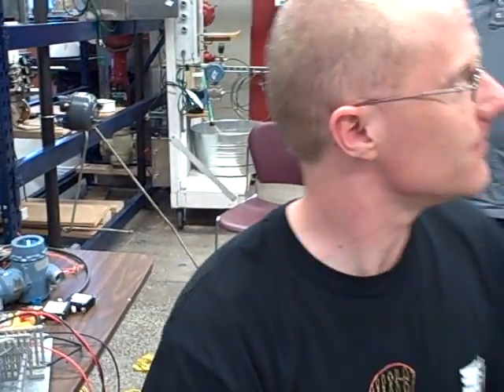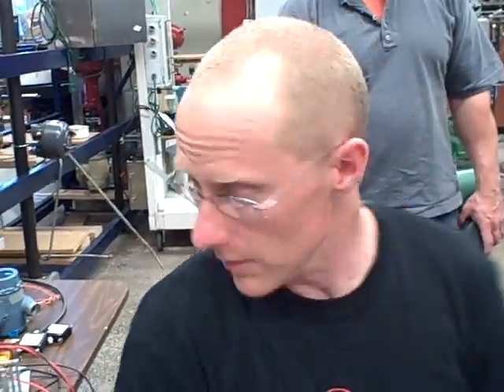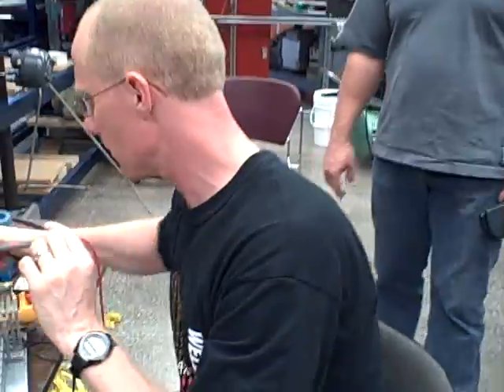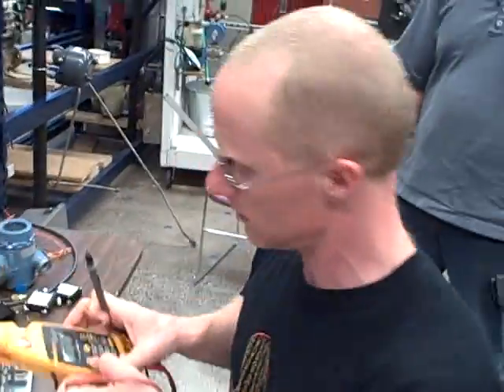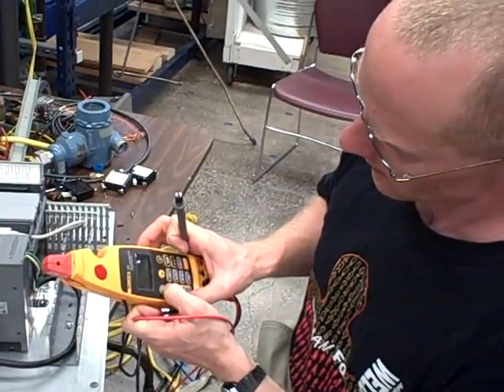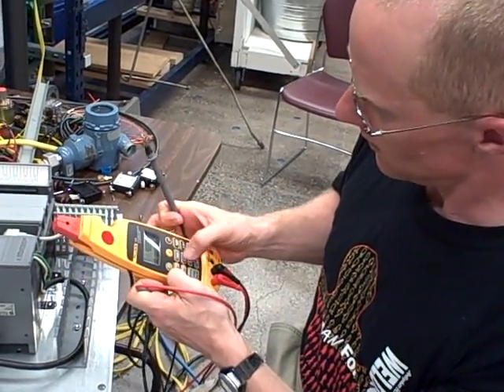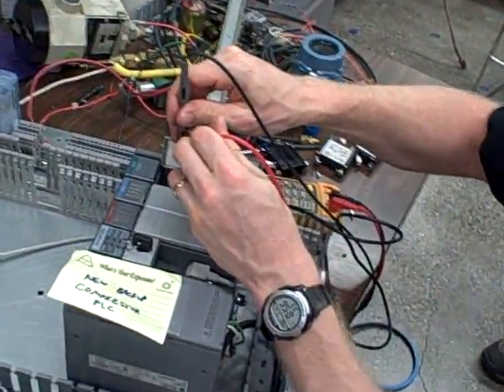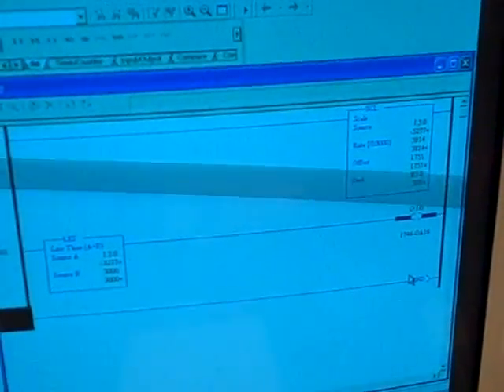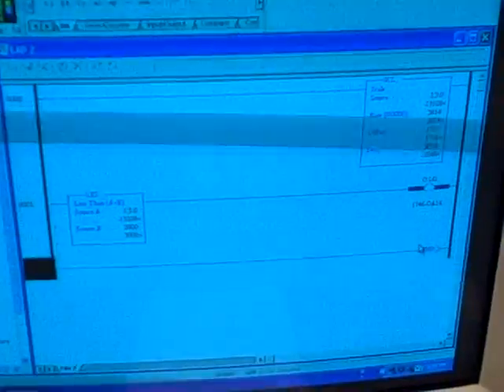I'd like it to go negative. I thought that's kind of cool, but that's not how we can. We can try that. We can try going negative here and see if we can actually read that. We can still read the raw count values. I'm going to turn this on again. Source. 4 milliamps. I'm going to go backwards. So let's see what sort of count value we get here. Looks like, yeah, source, minus 3,277. See that? And now I'm reading that right on the raw input, minus 3,277. And then I'll go up in milliamps. So there's 8 milliamps. There's minus 6,554. There's minus 9,831. So it's measuring negative milliamps too. Cool.